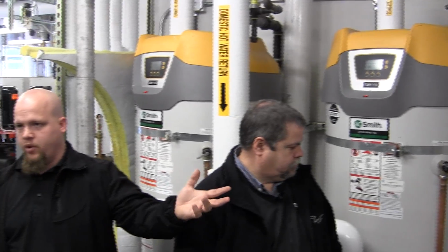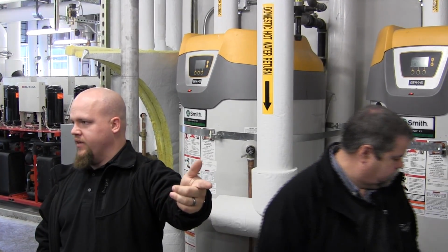And is that your storage tank? Yeah, we've actually got two storage tanks, one for solar, one for hot. This is your hot. Yeah. They're both AO. This one's insulated inside, but you want to take advantage as much as you can. It basically adds capacity to the system by having the storage tank. And then on the solar, same thing. You want to take advantage of that because during the winter, it gets dark at 5, 6 o'clock. All the students are taking their showers at 7, 8, 9 o'clock. So you want to be able to store that heat in an insulated tank and then use it when there's no sun. So this one here is for the domestic.